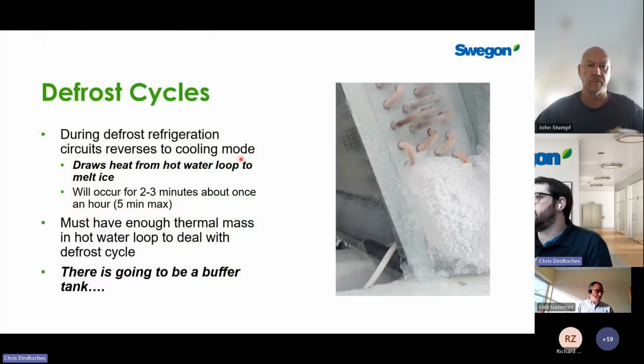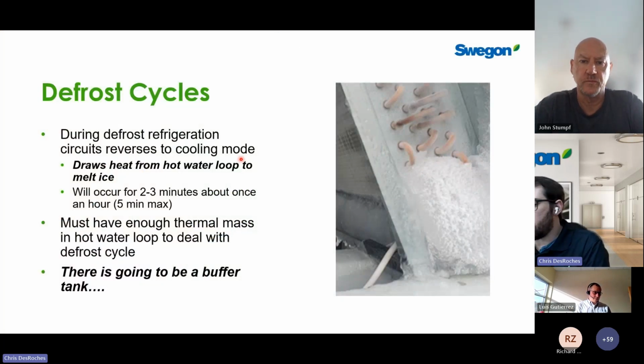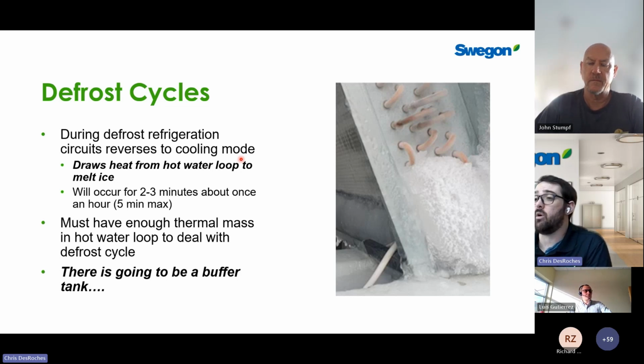So when it comes to defrosting, it's quite a loaded topic, and you can reach out to your friends at Long. This is a really condensed version of this to talk about. We could talk about defrost for an entire hour, lunch and learn. But really, when it comes to defrost, there's the water temperature stability we need to consider in our building and managing the condensate. So as you know, for any kind of heat pump, if we are cold outside, in order to extract heat, we have to send refrigerant to the coil. That's typically 20 F colder than whatever the air temperature is to get heat transfer from the air into the refrigerant circuit. So if our refrigerant temperature is below the dew point, we're going to get condensation from the air, and that's going to freeze and stick to the coil. So temporarily for 2 to 3 minutes, about once an hour or so, we're going to need to put the unit into a defrost cycle, which means even though it's a heat pump, we're temporarily putting it into cooling mode to melt the frost and ice off the coil.